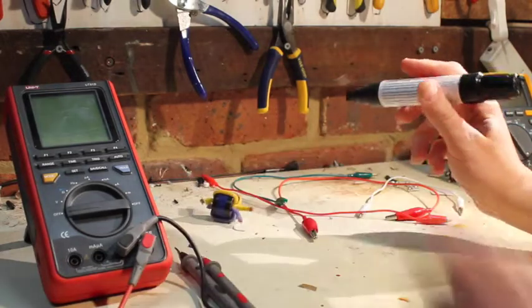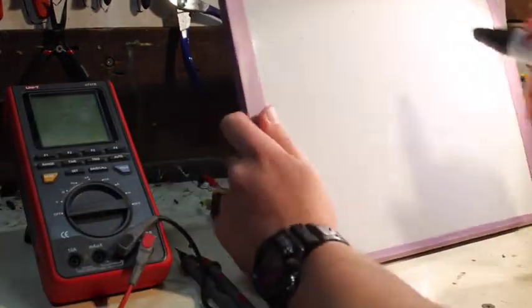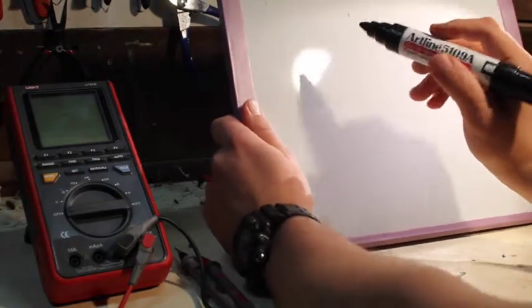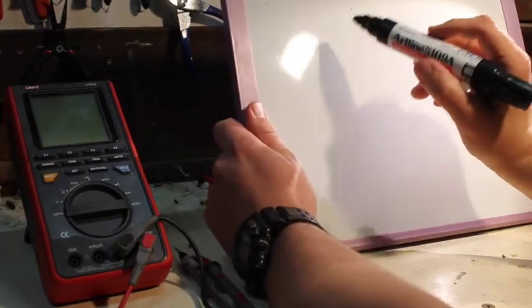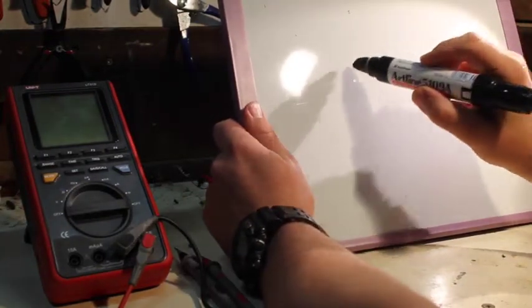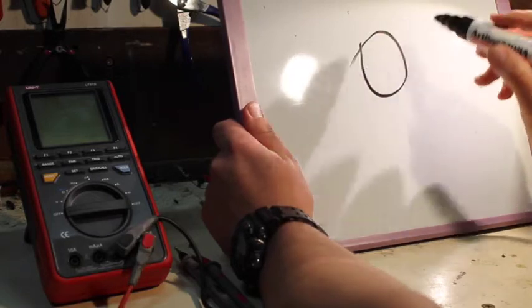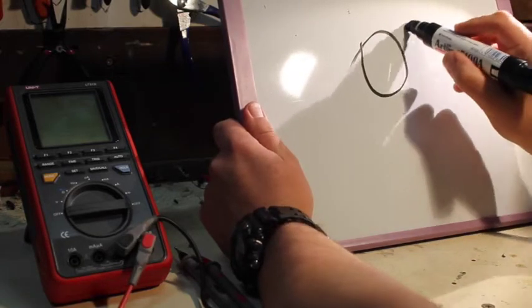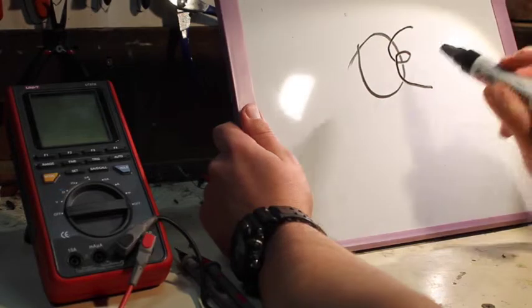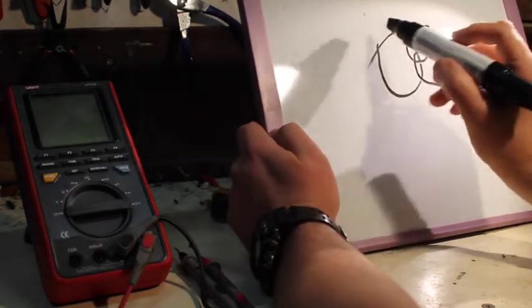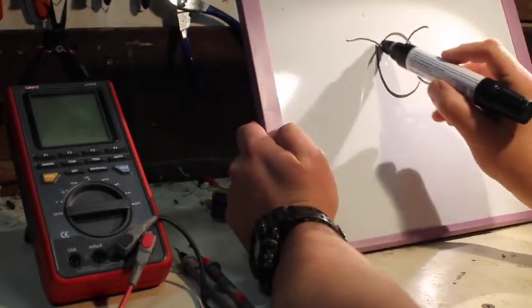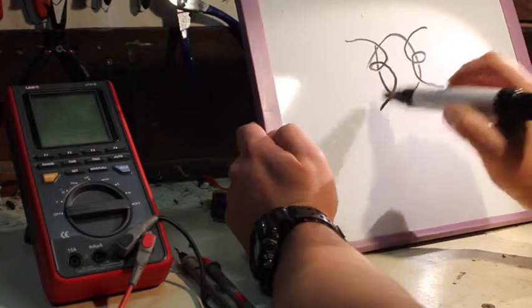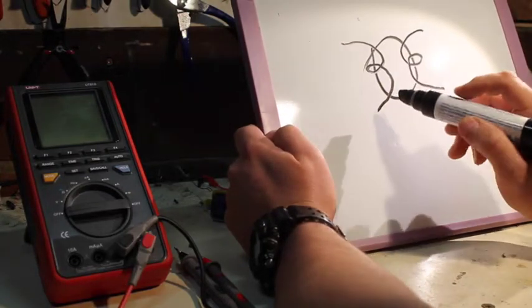What I'm going to do is I'm going to take this device and I'm only going to connect the active side. So if we think about our toroid here, we've got the neutral winding that comes in and I'm going to leave that disconnected. We're going to have the active winding going through there and any current that we put in the active will be an imbalance.